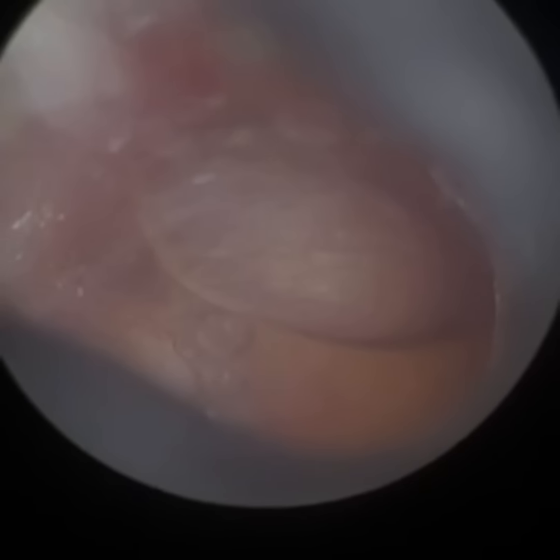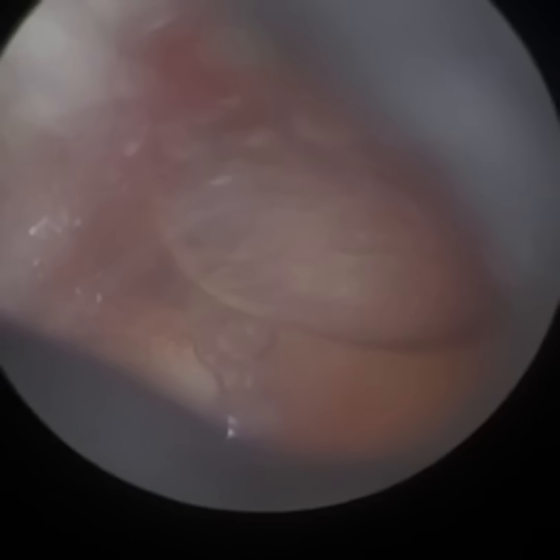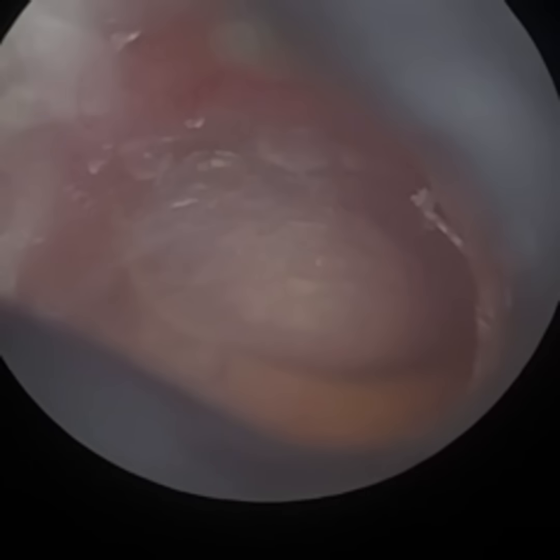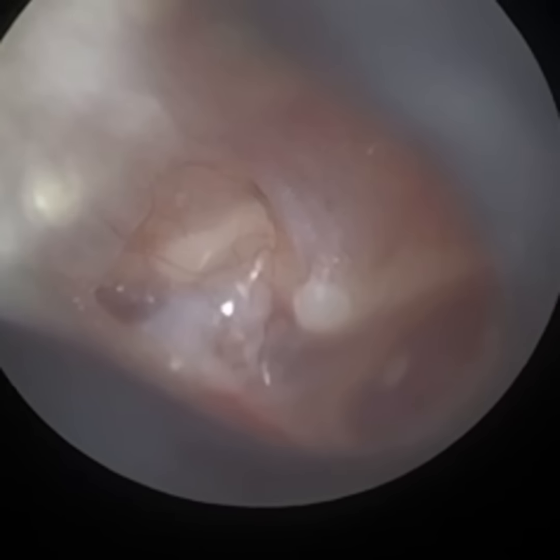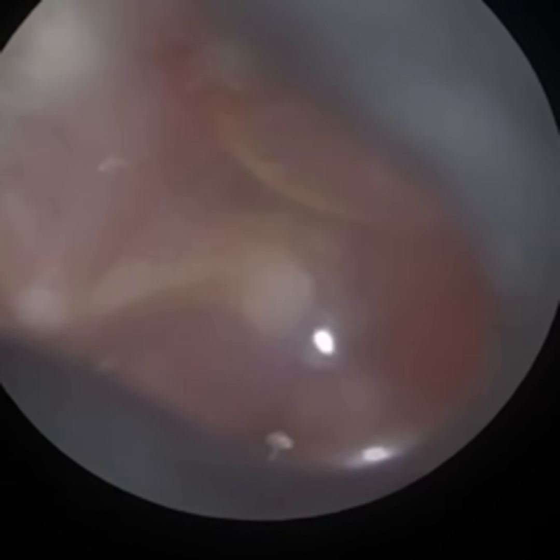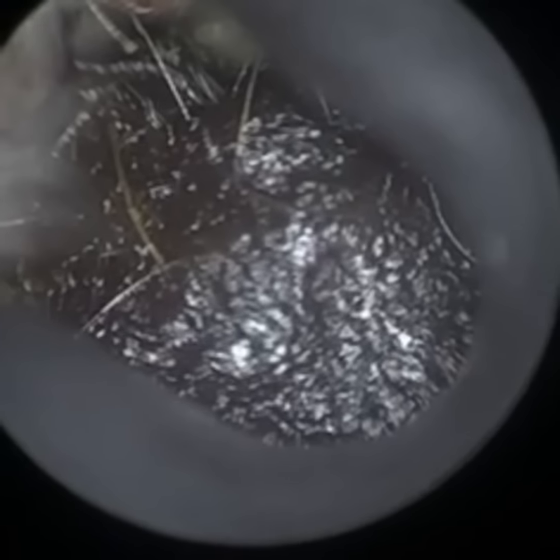Now, there is other technology that uses a speculum and a screen like what we've got here, but with that device, they're limited in certain ways. You can only use microsuction. You can't use other instruments like what we've just used here, an ear hook. Sometimes you're having to hold that suction device not from the handle but from the suction tubing because of the way the device has been developed. There's just not enough space. So it really reduces the manipulation available when you've got the instrument in the ear. And I personally wouldn't want anyone in my ear not holding the instrument as it was intended to be held.